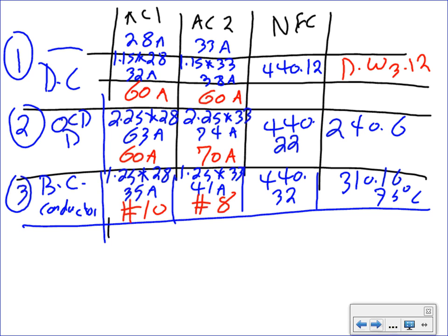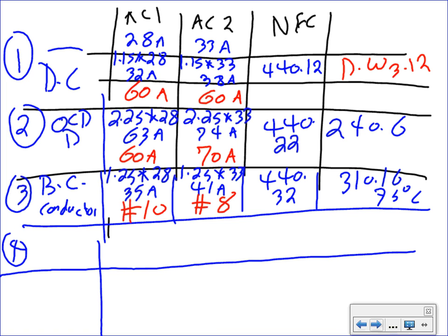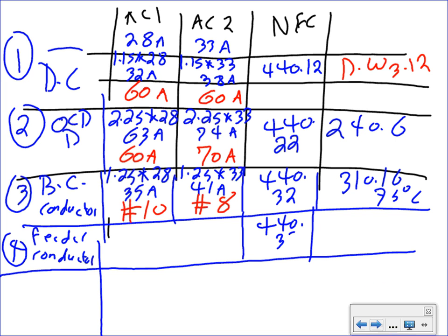Any questions, guys? So it's straightforward, right? Number 4, DJ. We didn't hit all 4. Feeder conductor. For feeder conductor, guys, you're going to go to 440.33. If you read through 440.33, it will tell you 125% times the largest motor plus all the others with it. Piece of cake.